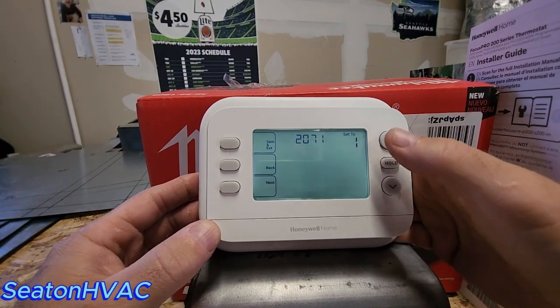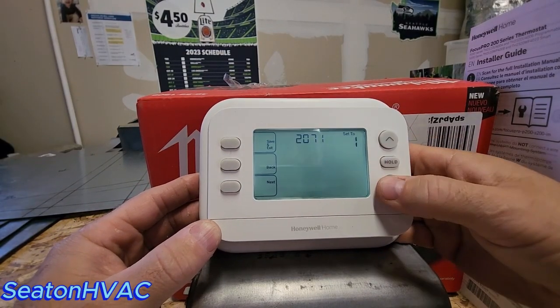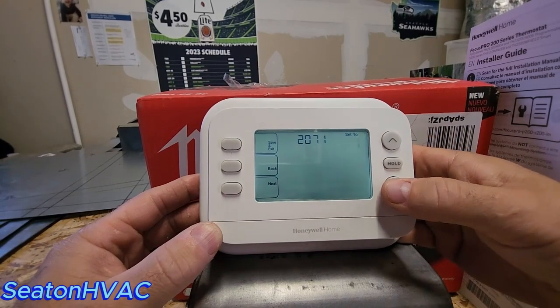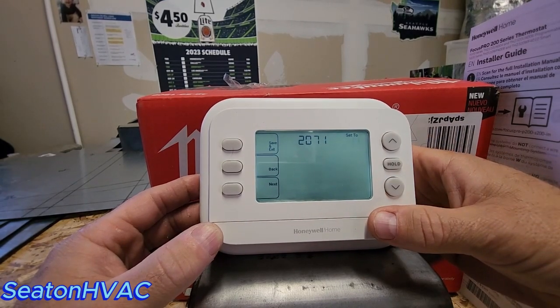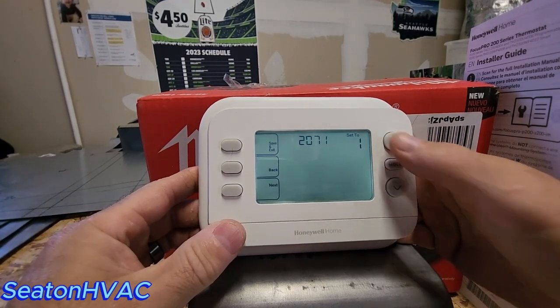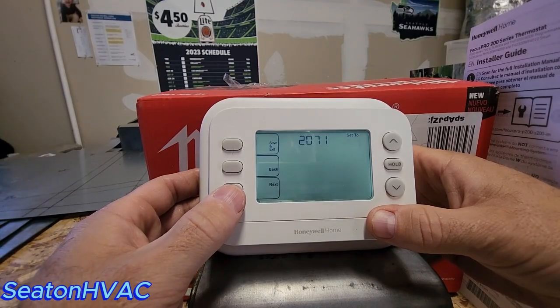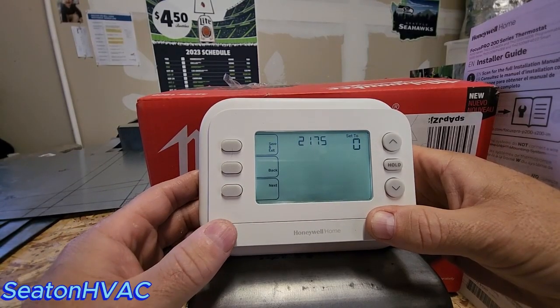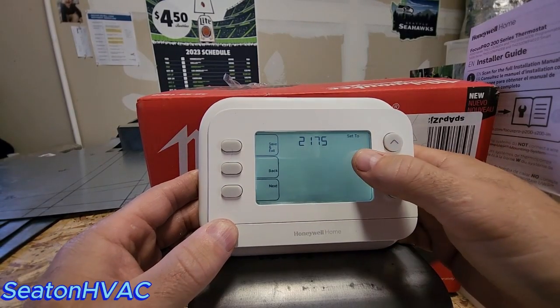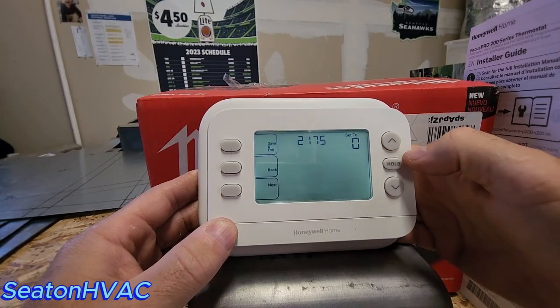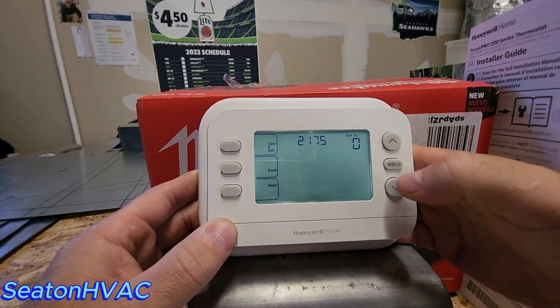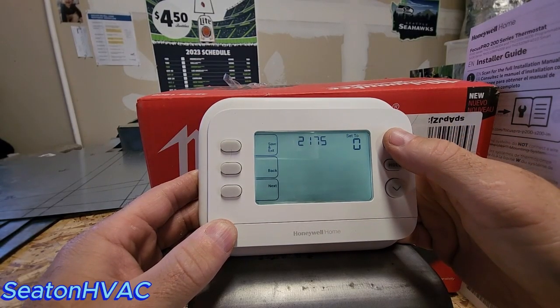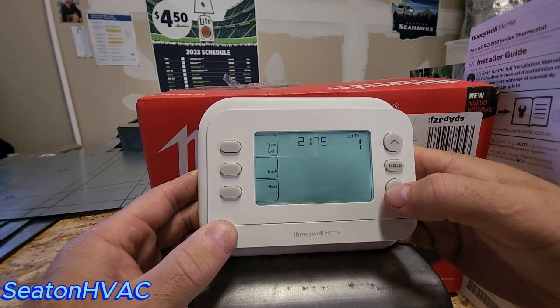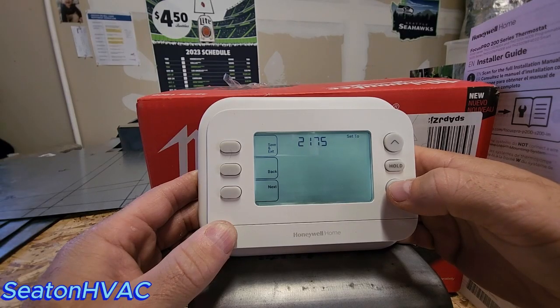And your backup heat, we have 1 stage of backup heat. If you had 2, you can toggle it to 2, but it won't do that on this because I already have 2 stages of compressor. So it'll only do 1 because this only does up to 3 stages. Auxiliary E terminal. Okay, so 0 is to drive them both together. Remember I was telling you that it does that. If you want them separate, you wanted your emergency heat separate from your auxiliary, then you hit that 1 and that breaks it up so they don't drive the voltage to both terminals at the same time.